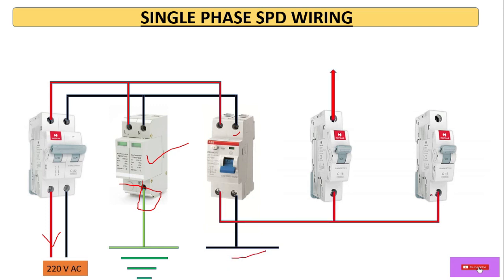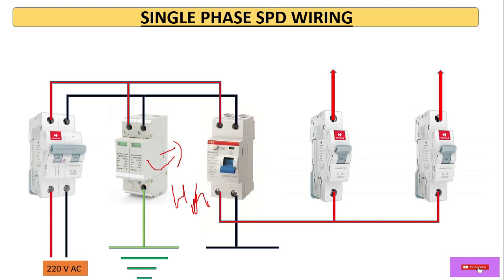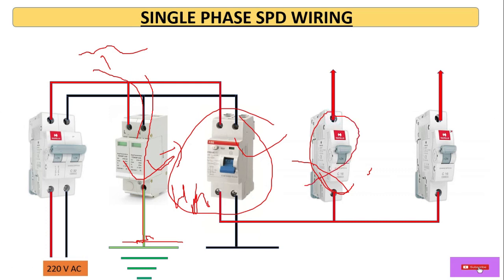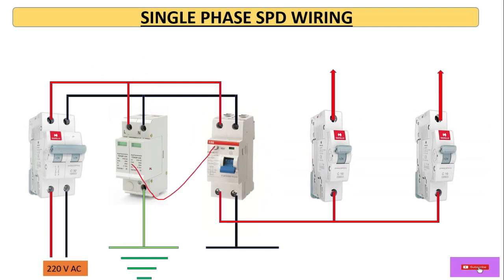From here, the neutral goes to the neutral bus bar and the phase goes to individual MCB circuits for the loads. During normal operation, the SPD is in high impedance state and loads operate normally. When any transient voltage or surge current occurs, its impedance decreases and it diverts the surge current and transient voltage towards earth for a short time — hence the loads are kept safe from transient voltage and surge current.